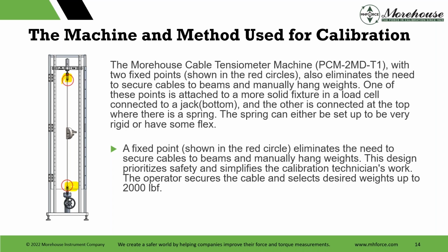And one of these points is attached to a more solid fixture in the load cell connected to the jack, and the other is connected to the top where there's a spring. The spring can either be set up to be very rigid or have some flex. Now, if it has some flex, we typically find that this machine is not very good for 10 pounds, 10 to 20 pounds. Sometimes you can get a 20-pound reading, but really, really low tension, because of that deflection, you often need to do something else.